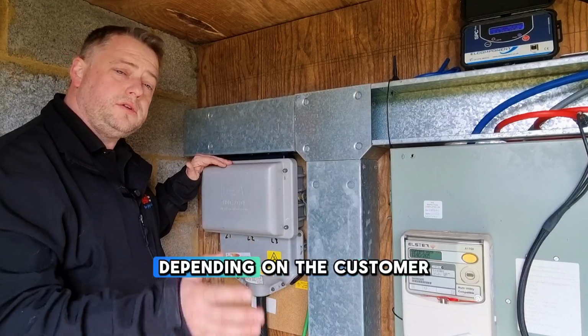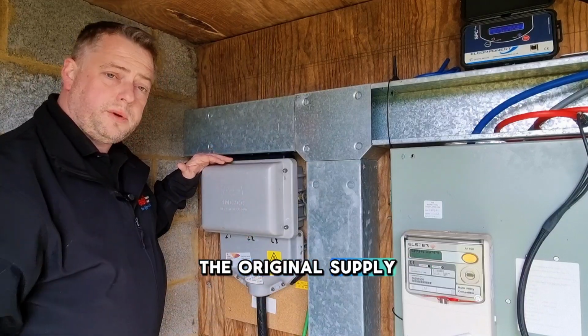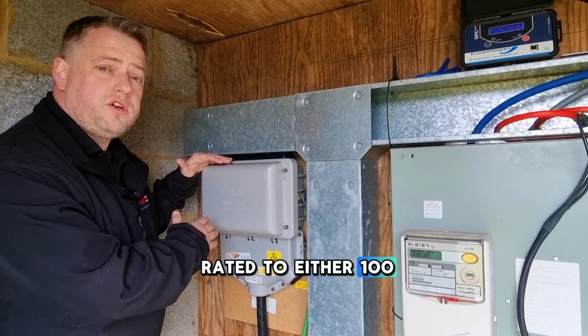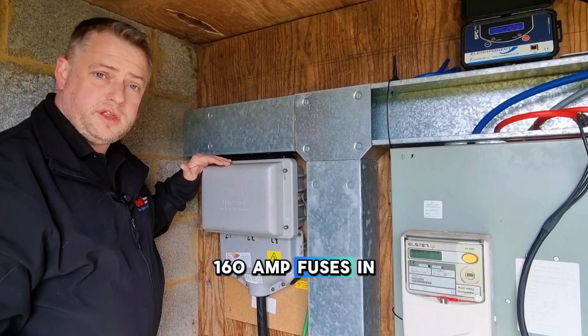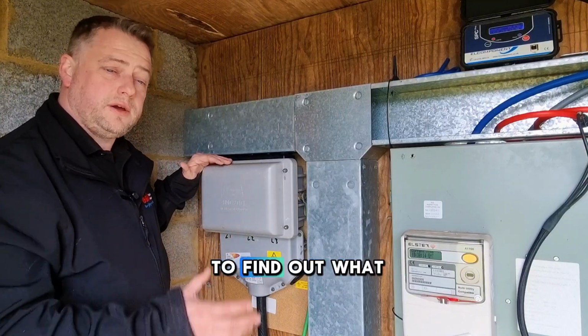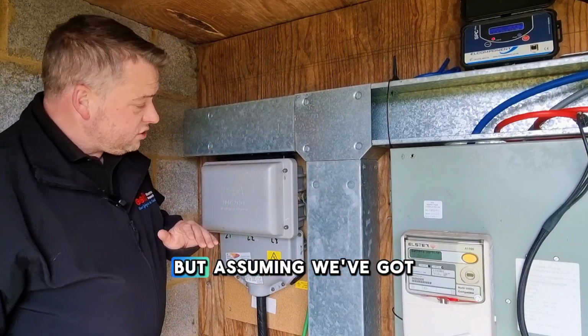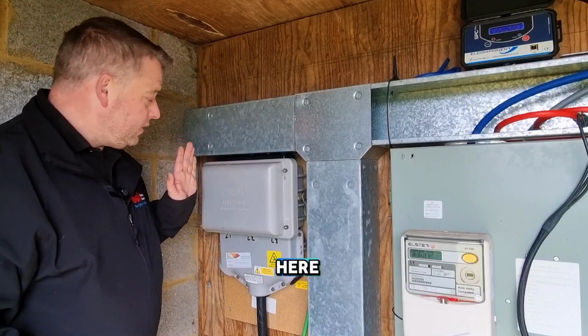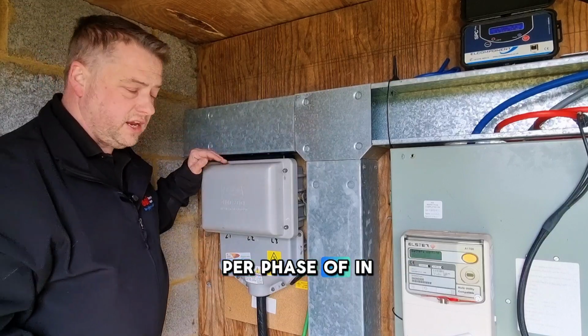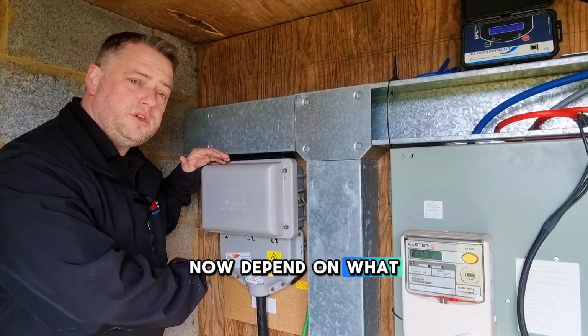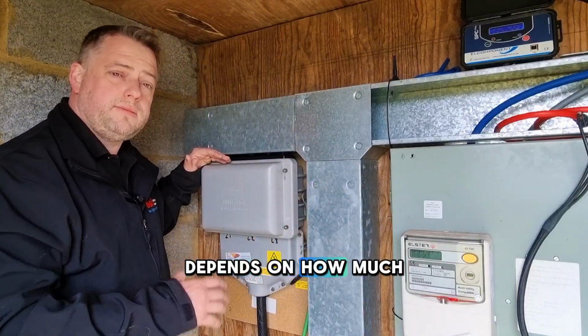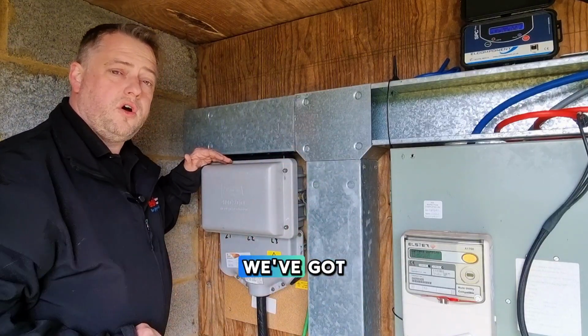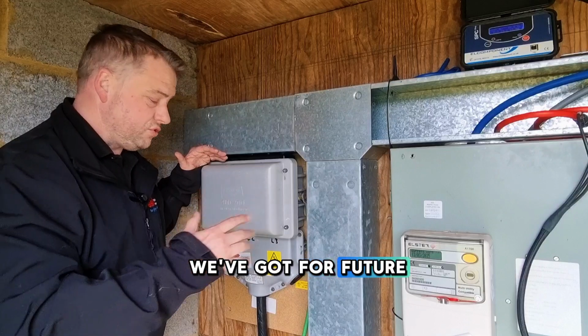On occasion, depending on the customer and when they applied for the original supply, they could be downrated to either 100 amp or 160 amp fuses. Sometimes we have to inquire to find out what it's been rated to. But assuming we've got 200 amps coming in, we have 200 amps per phase of incoming supply. Depending on what we use throughout the site, that determines how much baseline load we've got and how much capacity we've got for future expansion.